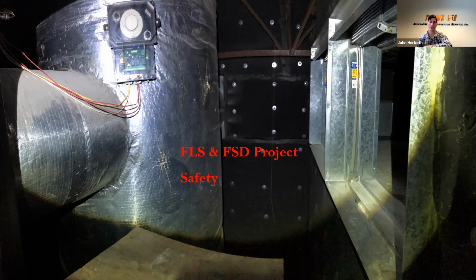So smoke control systems, I'm about to do another one in March of this next year. This is part of being a fire alarm commissioning agent. And you approach the aspect where you have to test those as a requirement. You have to test whether or not it's done at the fire alarm or fireman panel with the override controls to a whole system, and all those devices are connected to it, and then you have to test whether a switch out in the field fails.